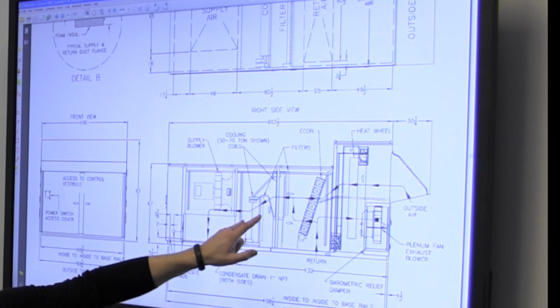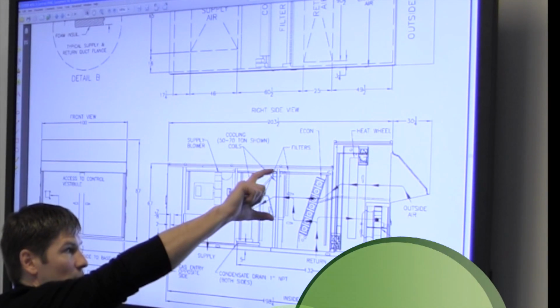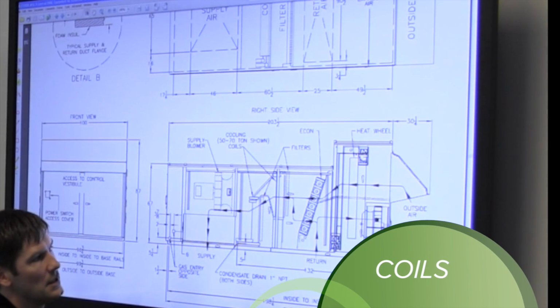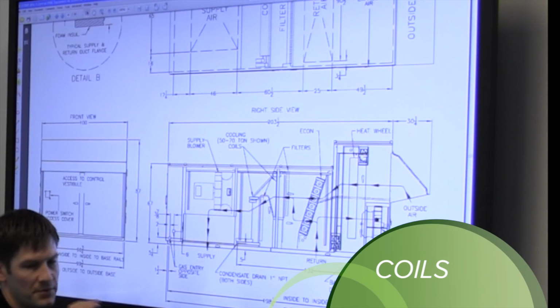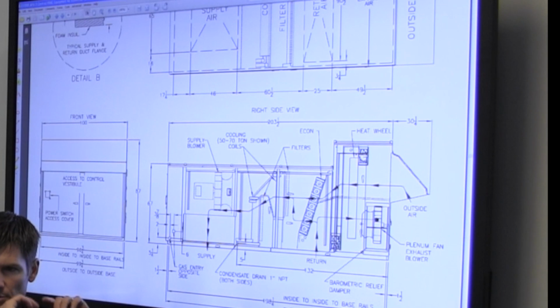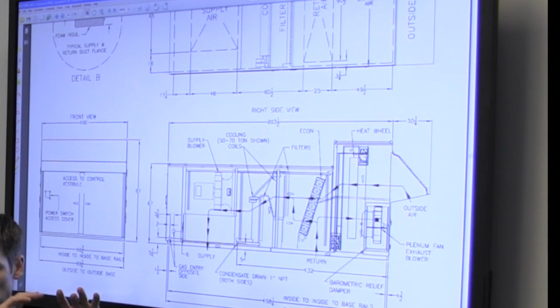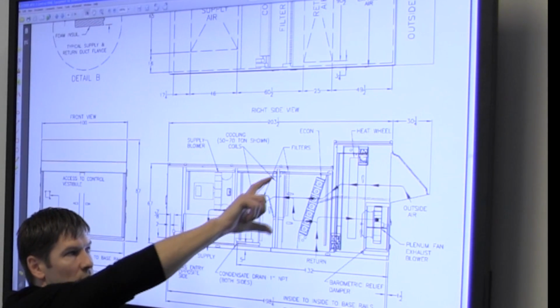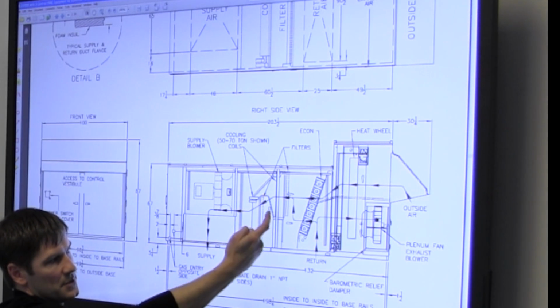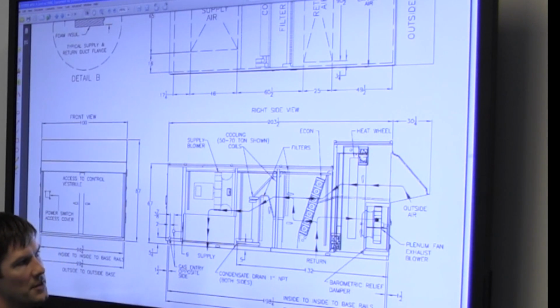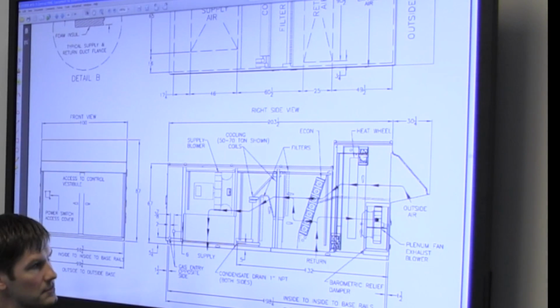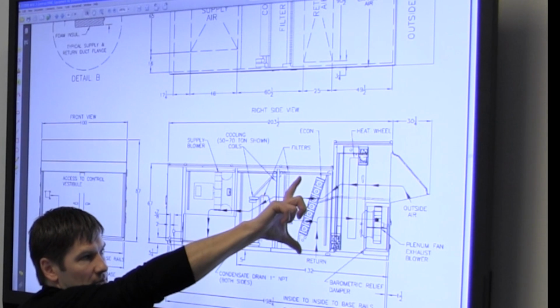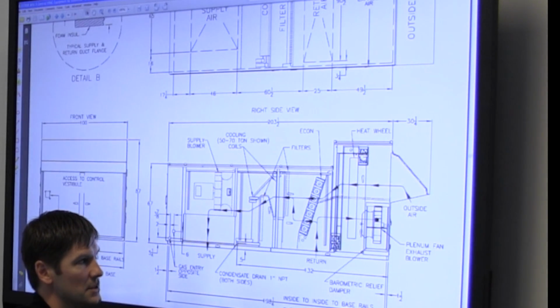Then we come through a staggered coil. So there's a coil here and there's a coil here. With cooling coils, you want a certain face velocity, feet per minute, that goes through the coils. If you go over 500 feet per minute, you spit out the condensate, and it causes issues. So what they've done here is they've made 2 large coils, and they staggered them. They put the sheet metal in between so that the air slows down and goes through the coil at 500 feet per minute and then speeds back up. And so this might be faster than 500 feet per minute, but at each coil, it's 500 feet per minute.